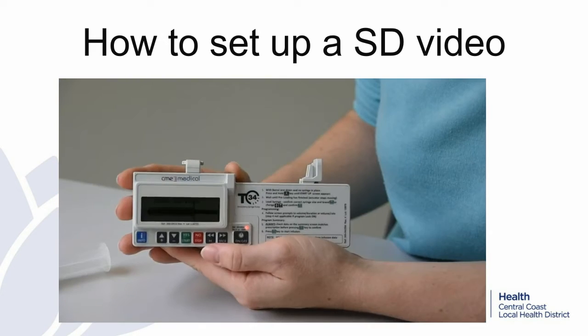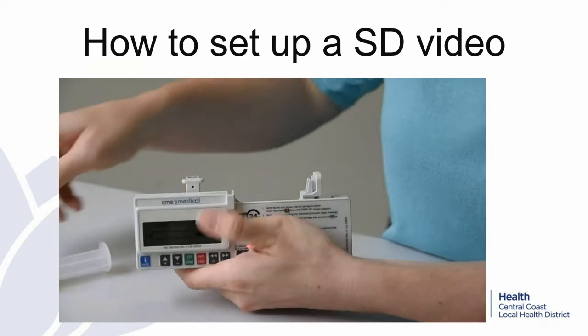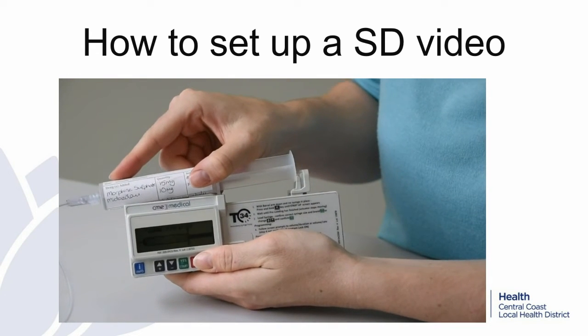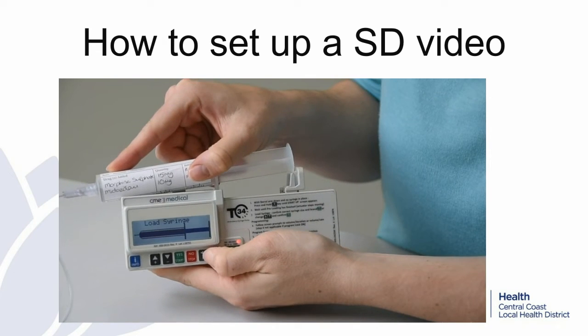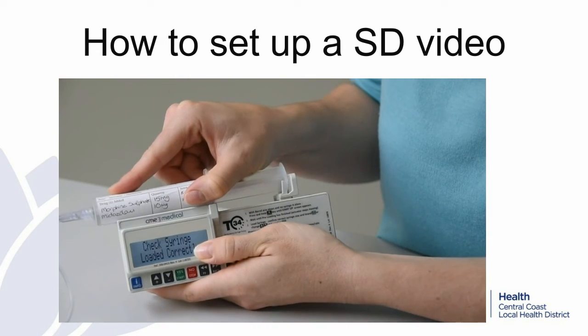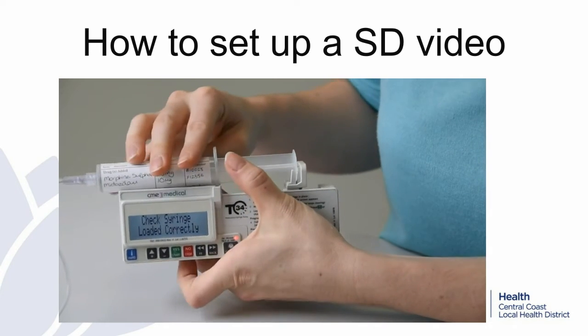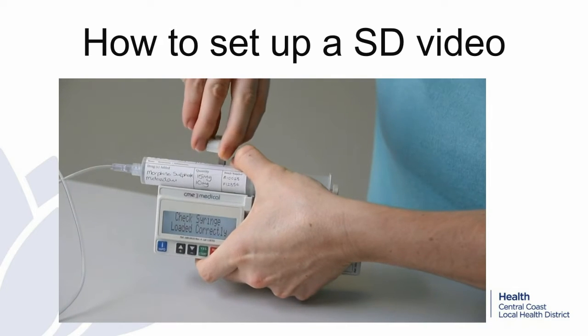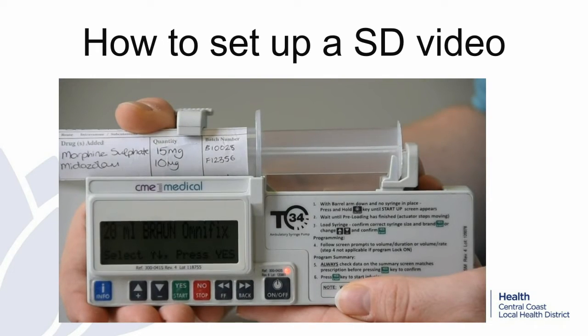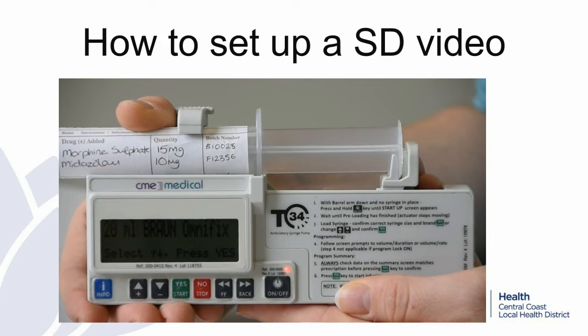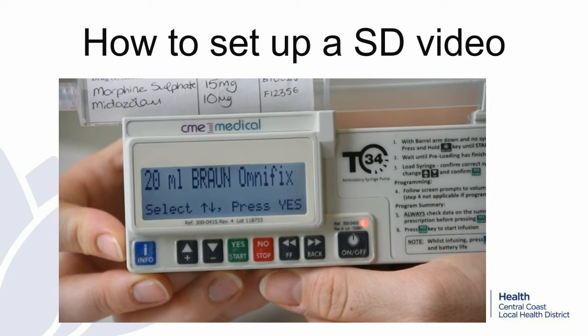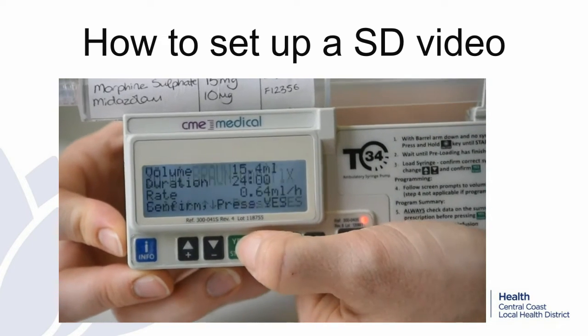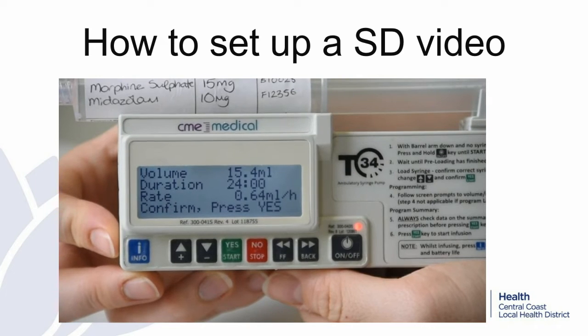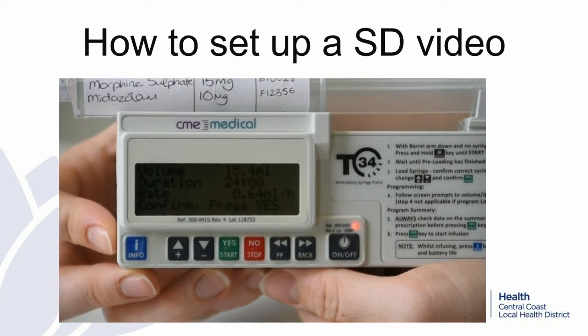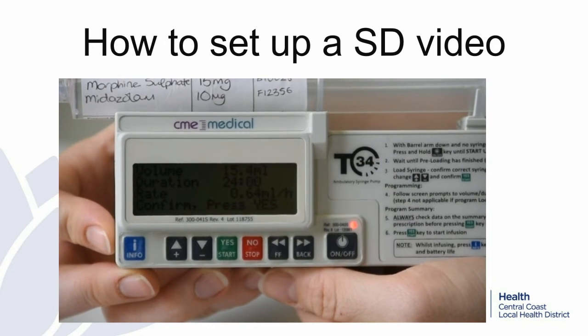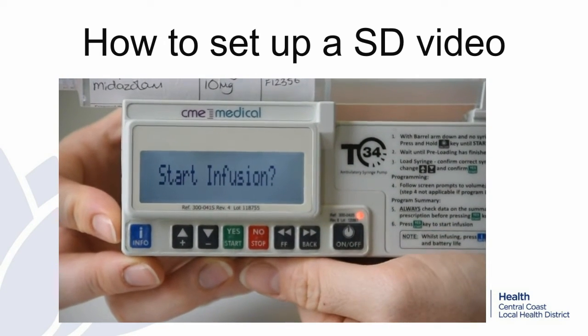To load the syringe, lift up the barrel clamp arm, line the syringe up along the barrel and use the arrow keys to move the plunger to the right spot. It is important for this to be accurate and not forceful, as not to waste any medication. Once the arm has been replaced, pull the barrel arm clamp up and over to secure the syringe in place. Once in place, on the screen it will tell you the brand of syringe, 20ml Braun Omnifix. These are preset within the hospital. You are asked to confirm this by pressing the yes button. The screen will then display the starting volume, duration of infusion and rate of infusion. Once you have written these down, press yes. The screen will then ask start infusion.